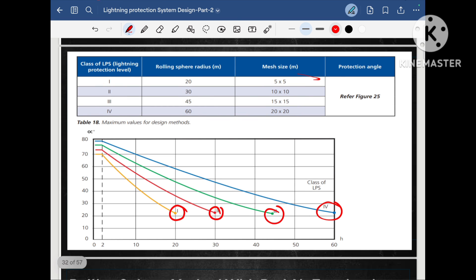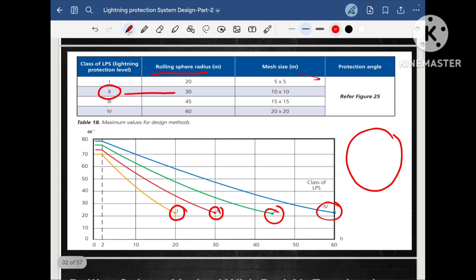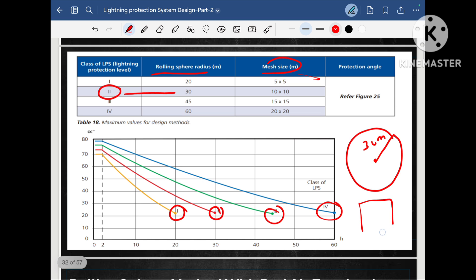To design the lightning protection system through the rolling sphere method, we imagine one sphere. Depending on the class, the radius will be different. For example, for our worker accommodation project with class 2 protection selected, we imagine a sphere with a radius of 30 meters. If we choose the mesh method for the same class 2 project, the mesh size will be 10×10 meters, meaning the distance between two mesh conductors is 10 meters from each other.